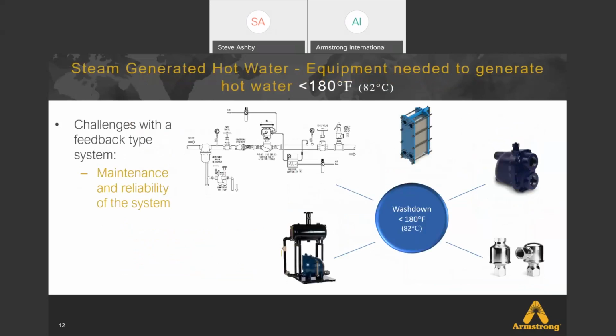So maintenance and reliability on this system, here are again the individual parts and pieces that make up these feedback systems. Certainly on the steam side, you have a lot of equipment required, all needing to work in sync to maintain temperatures. Then you've got your heat exchangers, steam traps, other ancillary items such as vacuum breakers and thermostatic valves. And then in a lot of instances, pumps are going to be required. So there's a lot of parts and pieces, a lot of intensive maintenance involved with these feedback designs.